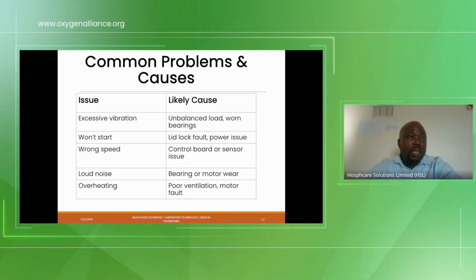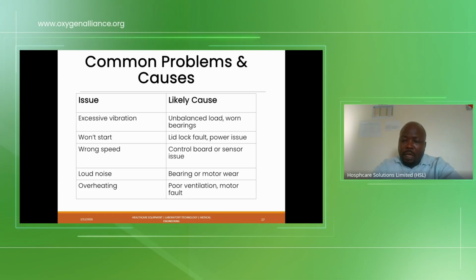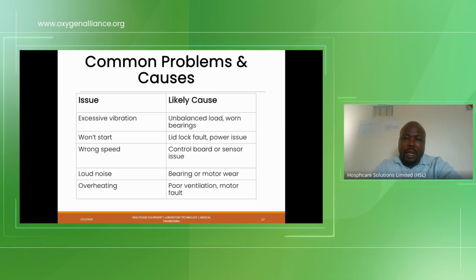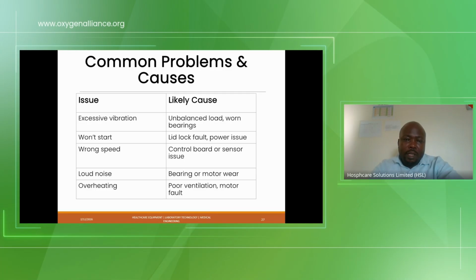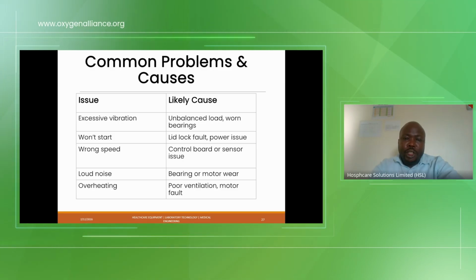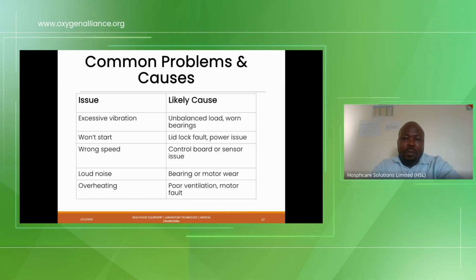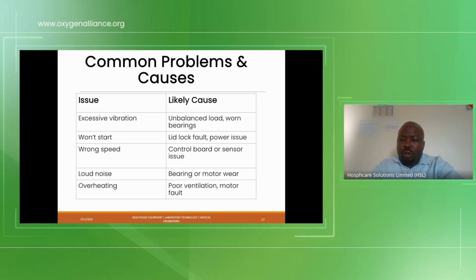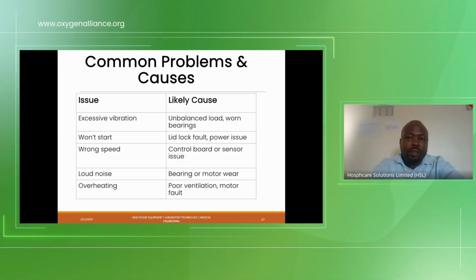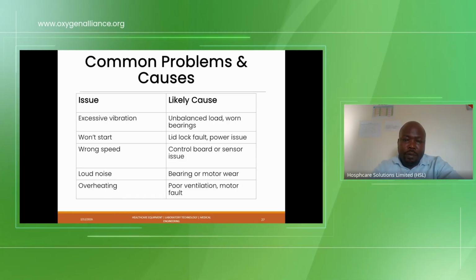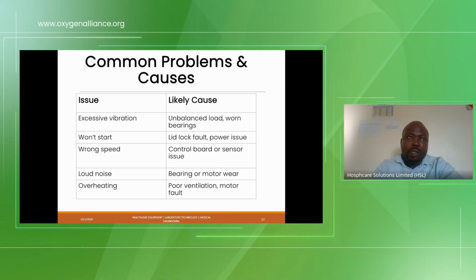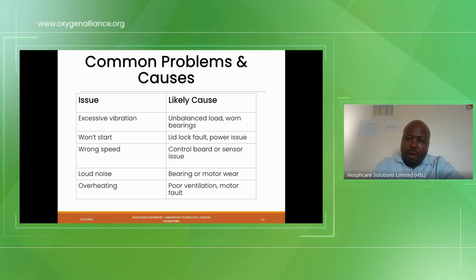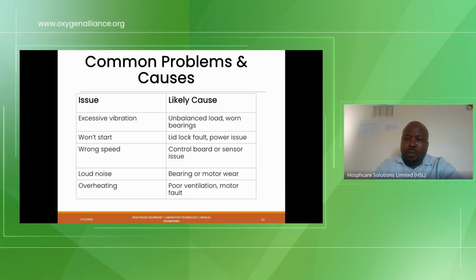Another common problem is loud noise. Once the machine is running, there will be a lot of generated noise. This indicates that the bearings or motor are worn out. We have wear and tear within the bearings or motors. We have overheating. This could be a result of poor ventilation or a fault in the motor, causing a heating effect from the machine. So probably the motor coil is gone, or in a refrigerated case, we just have poor ventilation.